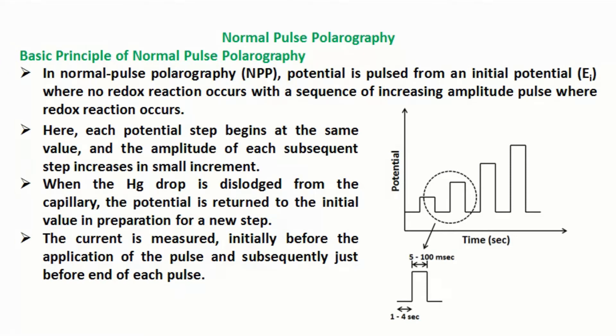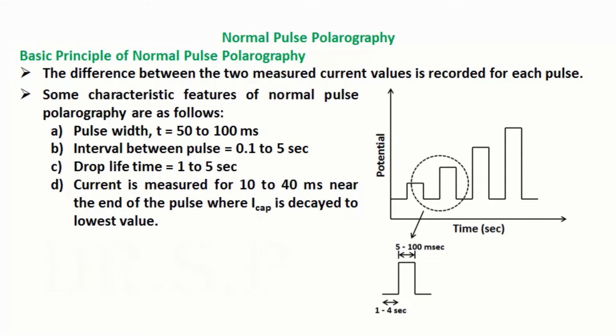The current is measured initially before the application of the pulse and subsequently just before the end of each pulse. The difference between the two measured current values is recorded for each pulse. Some characteristic features of normal pulse polarography are: pulse width T equals 50 to 100 milliseconds, interval between pulses equals 0.1 to 5 seconds, drop lifetime equals 1 to 5 seconds, and current is measured for 10 to 40 milliseconds near the end of the pulse where capacitive current ICAP is decayed to its lowest value.